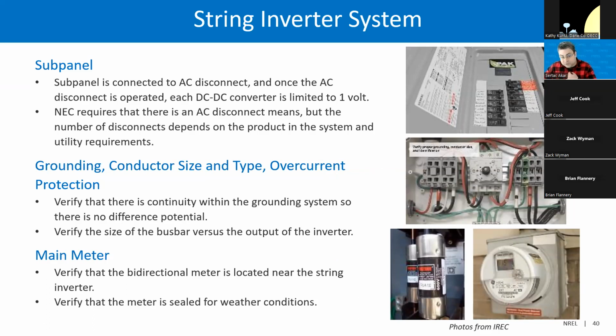The National Electrical Code requires a number of disconnects depending on the product in the system, and utility requirements should be in line with the NEC requirements. The inspector should verify the size of the bus bar versus the output of the inverter and check that there's continuity within the grounding system so that there is no difference in potential. The last thing to check is the main meter. Bidirectional main meters must be located near the string inverter and must be sealed for weather conditions. This can be seen in these pictures.